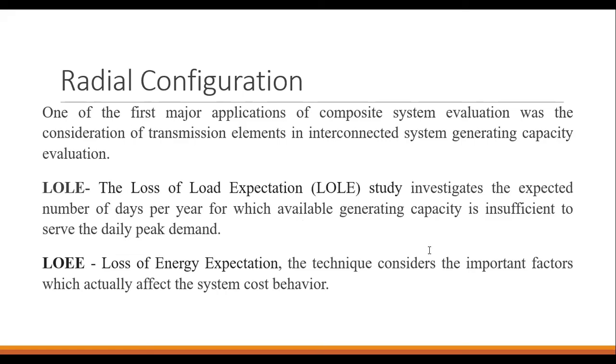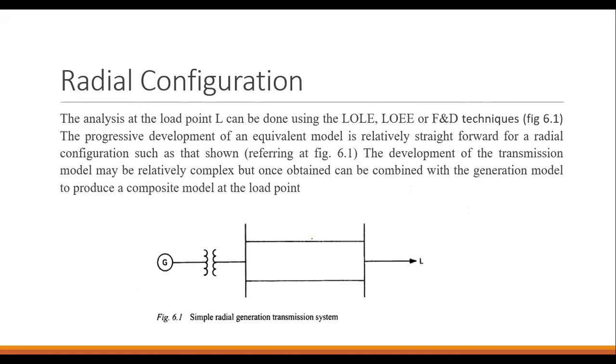LOLE, the loss of load expectation, is a study that investigates the expected number of days per year for which available generating capacity is insufficient to serve the daily peak demand. Also, we have LOEE, the loss of energy expectation. The technique considers the important factors which actually affect the system cost behavior. The analysis at load point L can be done using these terms, based on LOLE and LOEE techniques.